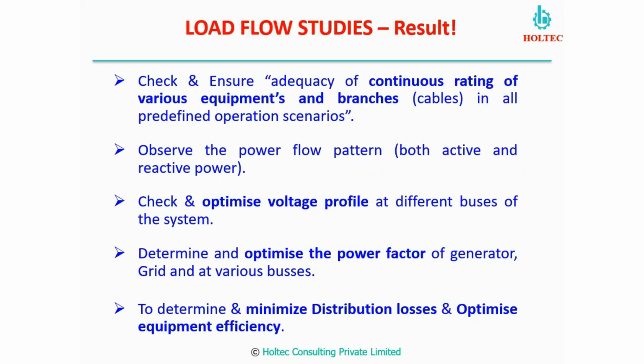Now coming to the load flow results. From the load flow results, we can ensure the continuous rating of the various equipment and branches, the bus bars or the cables. We can also observe the power flow pattern, both reactive power and active power, in the complete power distribution network. Then we can check and optimize the voltage profiles at different buses of the system. When we get the information on the voltage profile at different buses, based on the result we can suggest corrective actions to optimize the voltage profile.